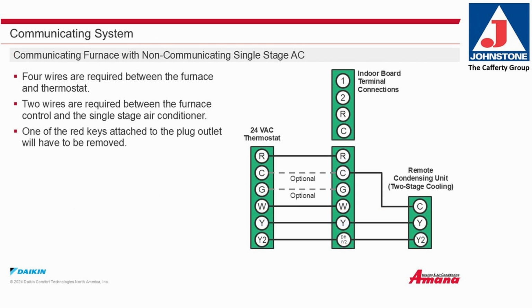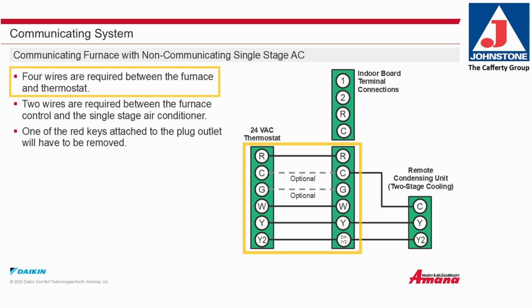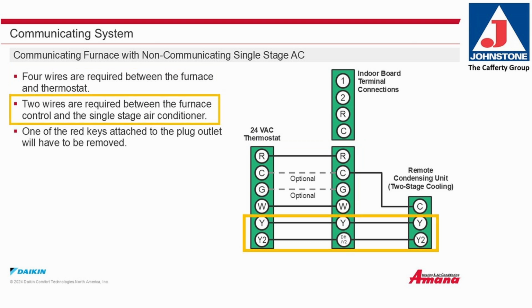Communicating system. Communicating furnace with a non-communicating single-stage AC. 4 wires are required between the furnace and the thermostat. 2 wires are required between the furnace control and the single-stage air conditioner. One of the red keys attached to the plug outlet will need to be removed.